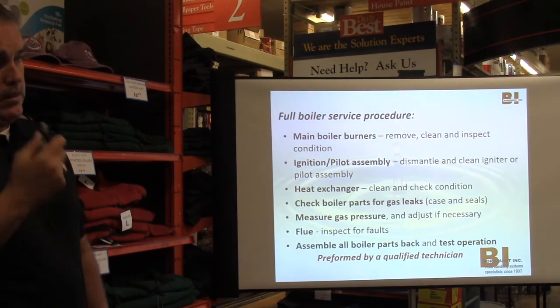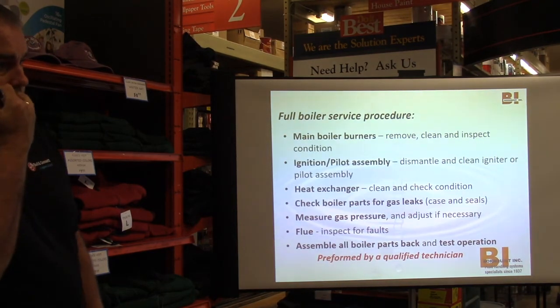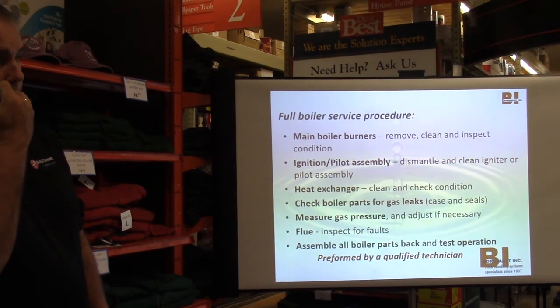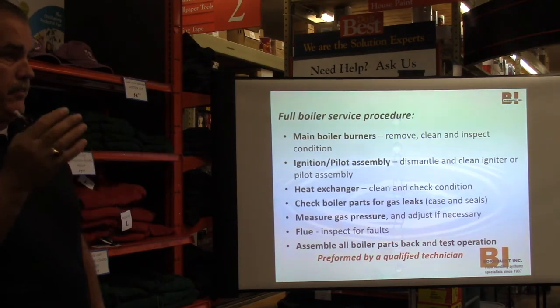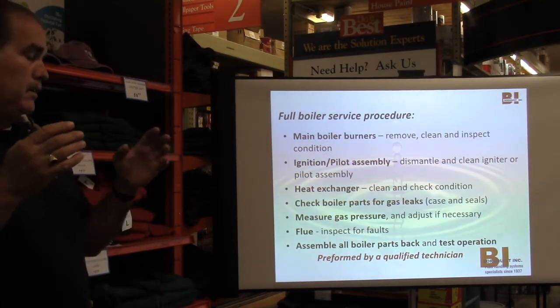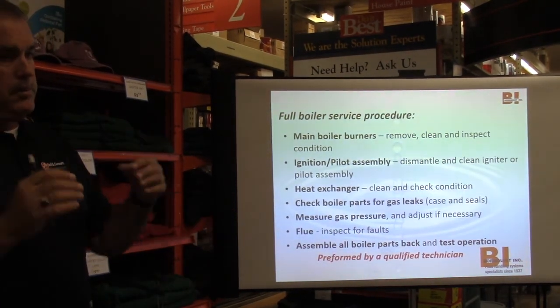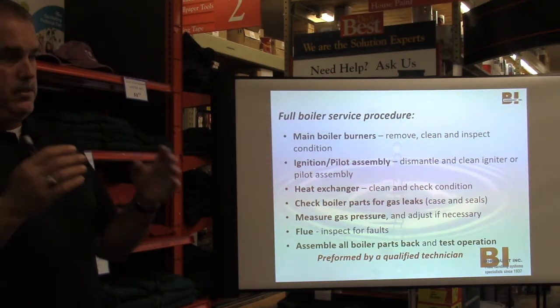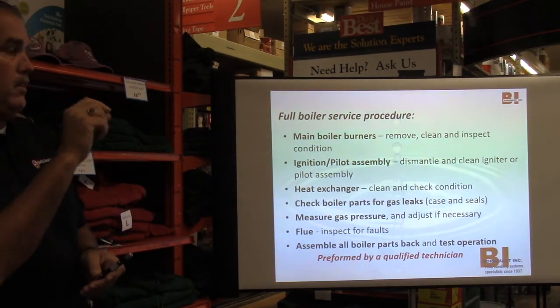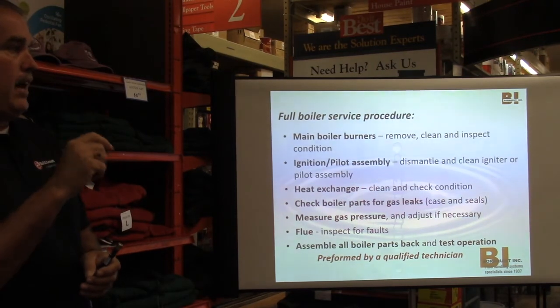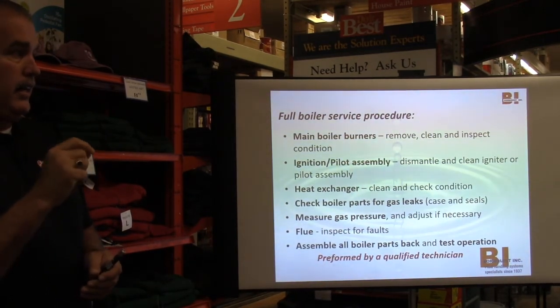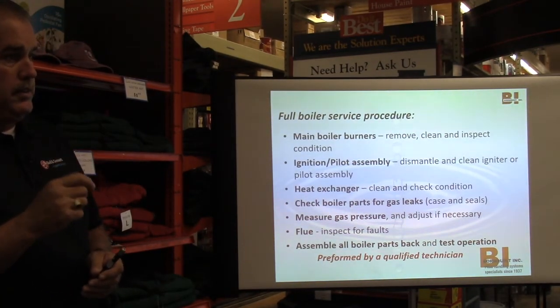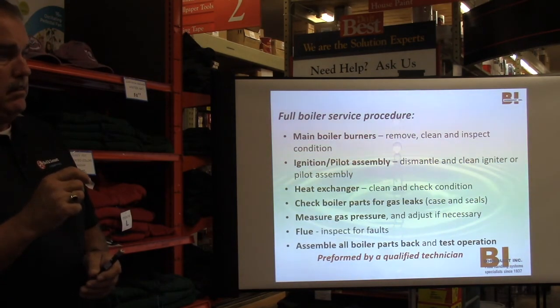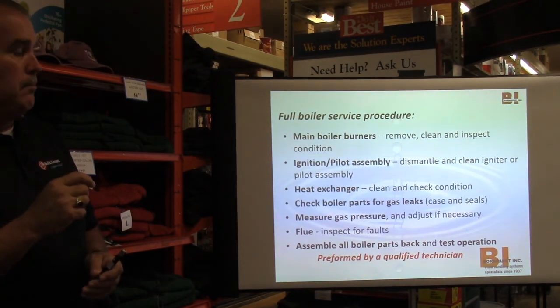Your flue, often ignored, very dangerous. I am not a big fan of plastic flue. The boiler maker, one guy started it and then everybody jumped on it, and now everybody says it's okay for smaller units. But usually nowadays, if you're going to use plastic, it certainly is not on an atmospheric boiler, because an atmospheric boiler needs B-vent. Metal B-vent, not plastic. It'll melt.